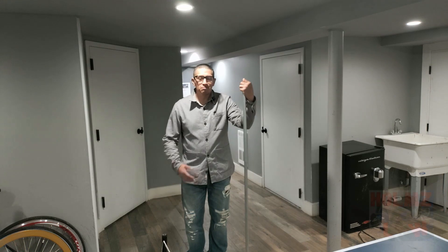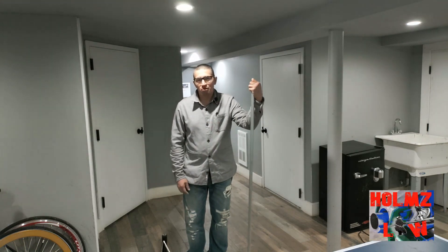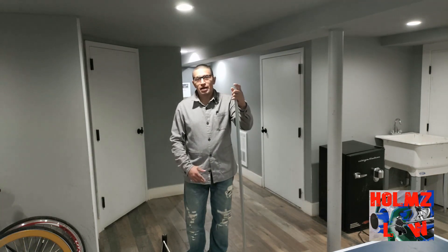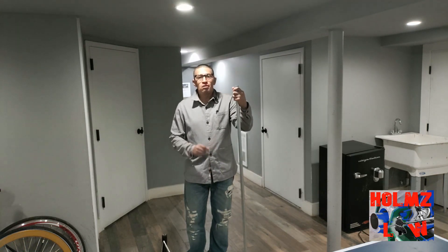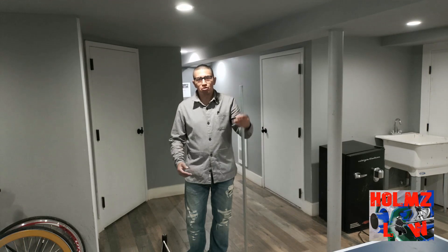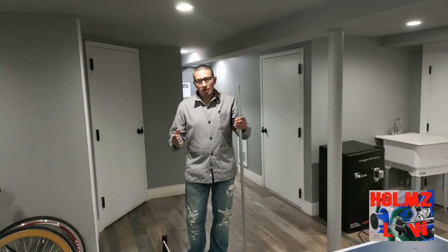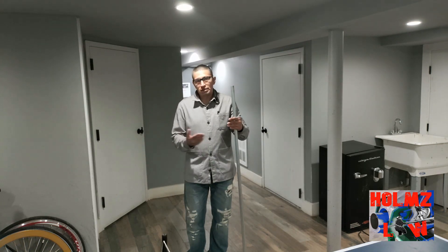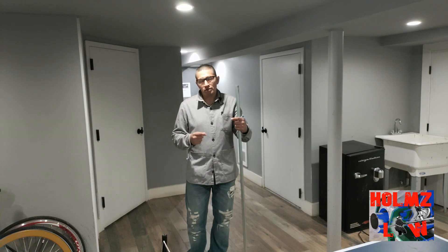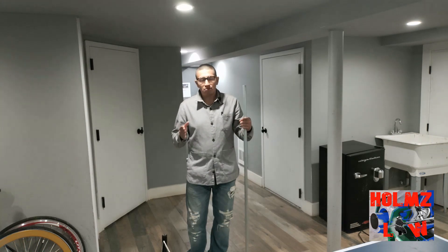Hey, what's up guys? My name is Mel, welcome to Holmz Love. Today I'm going to be teaching you a three-point saddle for those that have to go around small round obstructions. Sometimes you're going over something as small as one inch or three-quarters of an inch and your bends are just too close together. The solution is using a smaller degree — a three-point saddle. In this video I'm going to show you how to do a 22.5-degree three-point saddle, with 22.5 in the center and 11 degrees on the sides.